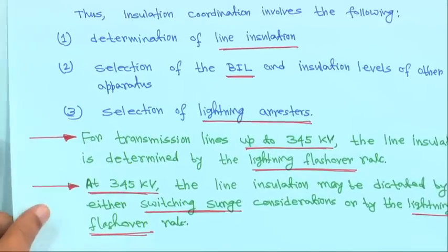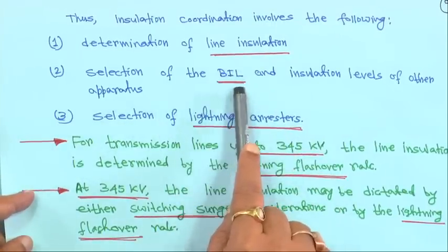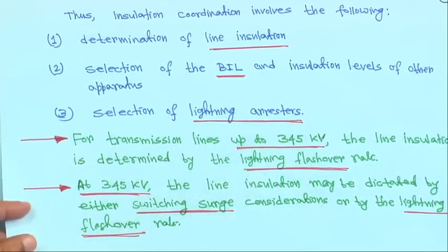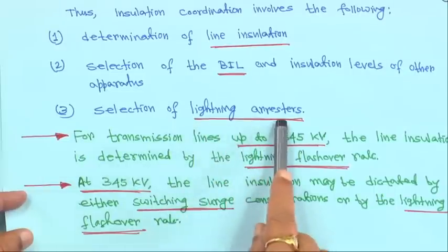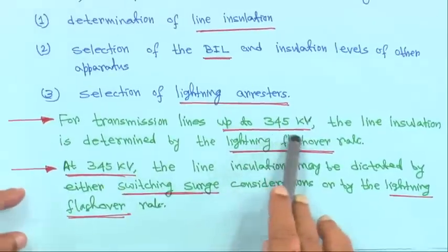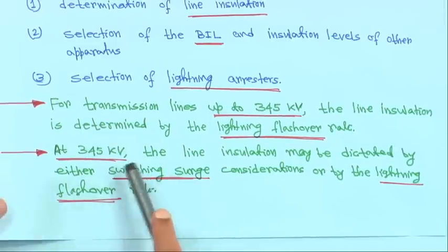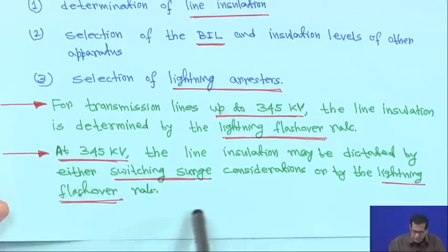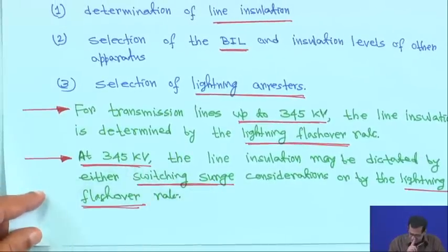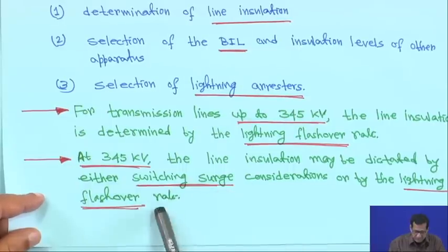Insulation coordination involves: determination of line insulation, selection of the BIL value and insulation levels of apparatus, and selection of lightning arrestors. For transmission lines up to 345 kV, line insulation is determined by lightning flashover rate only. At 345 kV, the line insulation may be dictated by either switching surge considerations or by the lightning flashover rate.